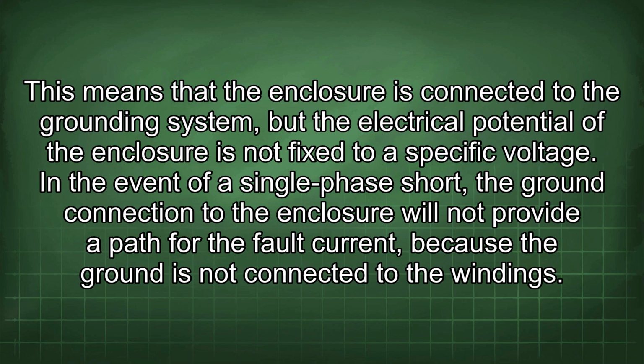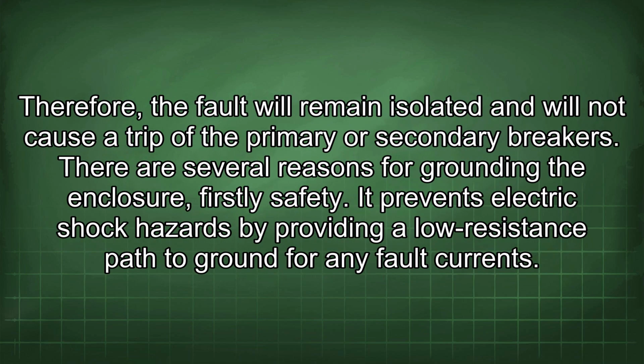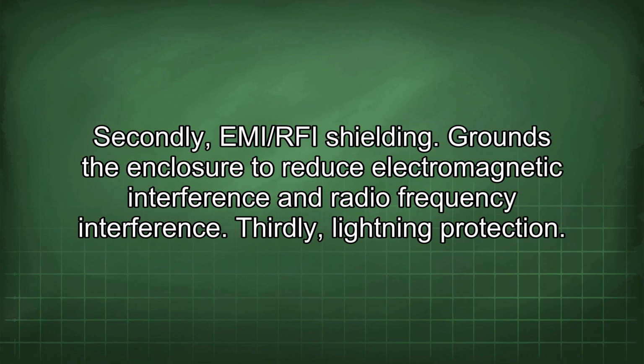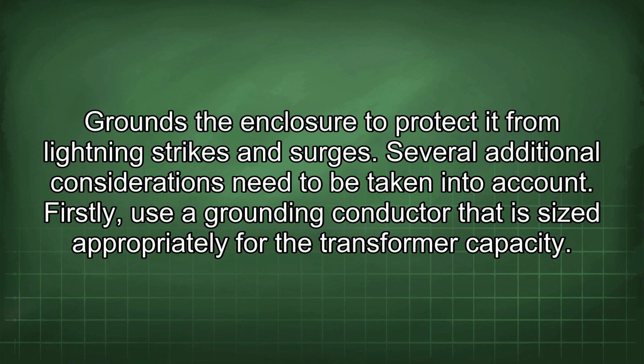In the event of a single-phase short, the ground connection to the enclosure will not provide a path for the fault current because the ground is not connected to the windings. Therefore, the fault will remain isolated and will not cause a trip of the primary or secondary breakers. There are several reasons for grounding the enclosure. Firstly, safety. It prevents electric shock hazards by providing a low-resistance path to ground for any fault currents. Secondly, EMI/RFI shielding. Grounds the enclosure to reduce electromagnetic interference and radio frequency interference. Thirdly, lightning protection. Grounds the enclosure to protect it from lightning strikes and surges.